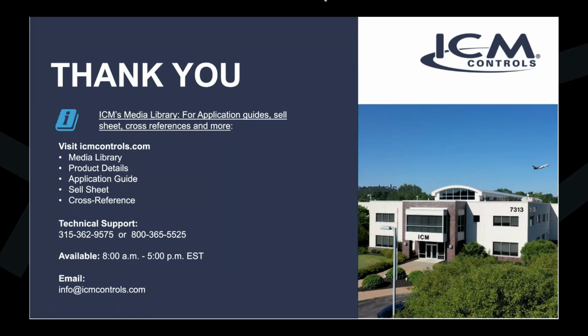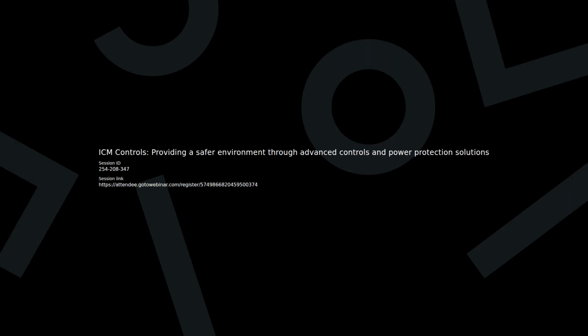To get started, we have a question: do you know why defrost is required with using a heat pump? The reason we use a defrost control is to provide operation of your heat pump in very cold climates. Otherwise, if you did not have a defrost board, your outdoor coil would freeze up, and you would have a problem with thermal transfer. So defrost boards are essential and required for heat pumps to be able to run them in cold climate conditions.